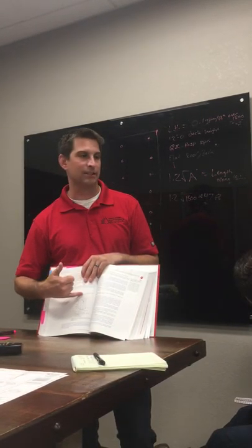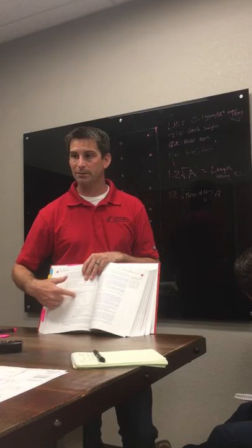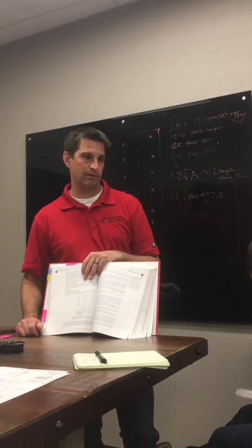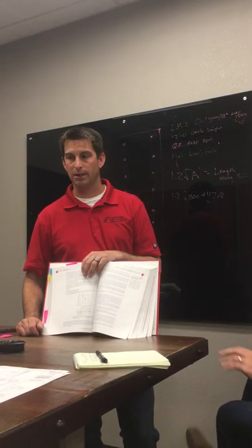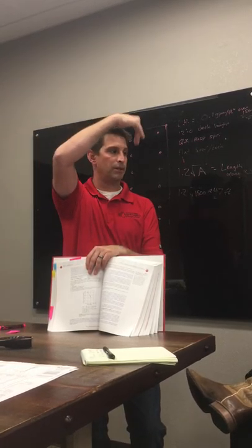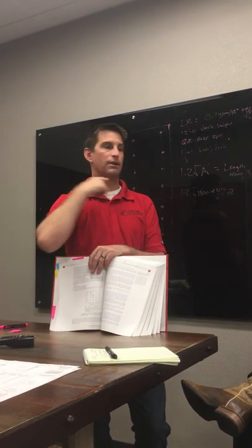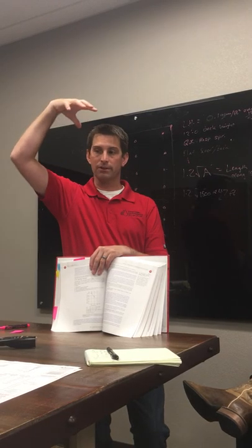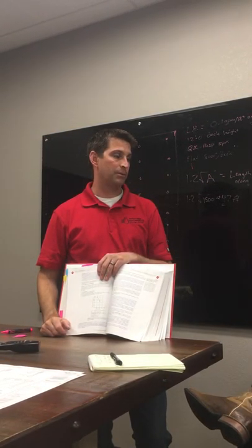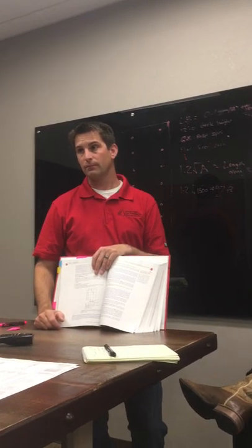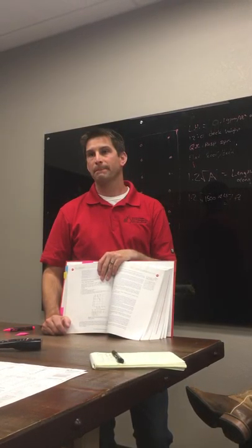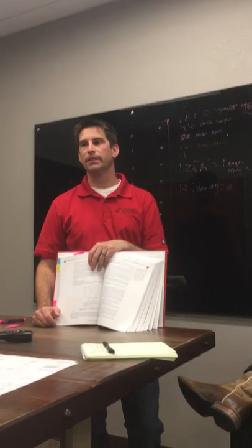No, this one gets overlooked a lot. Technically, if you're doing quick response reduction, you cannot have any unprotected ceiling pockets. If you have unprotected ceiling pockets, that's like, let's say, a conference room where the ceiling bumped up 2 feet in the middle and came back down, and you only had sprinklers around the outside, you didn't have sprinklers up inside that pocket, you couldn't do the quick response reduction. People do it all the time and it's wrong. So if you're saying that the ceiling that's higher is higher than 20 feet? No, it's more about pockets. We'll have to get into that with you.